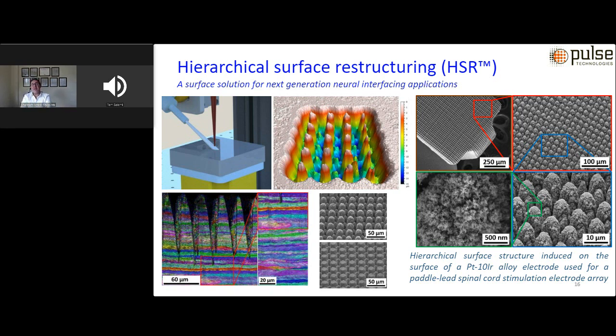Sure. The thinnest electrode that we've been able to work with successfully has been a very thin foil of platinum iridium used for a deep brain stimulation application, and the thickness of that was 1 thou, 25 microns. That has been restructured very successfully. I don't recall the exact number, and I don't want to mention one that is incorrect off the top of my head, but significantly we were able to increase the electrochemical performance of the foil electrodes, but obviously not to the extent where, for example, we could work with a percutaneous or cylindrical electrode, where the thickness is oftentimes 4 or 5 times that of a thin foil that is used for deep brain stimulation application.